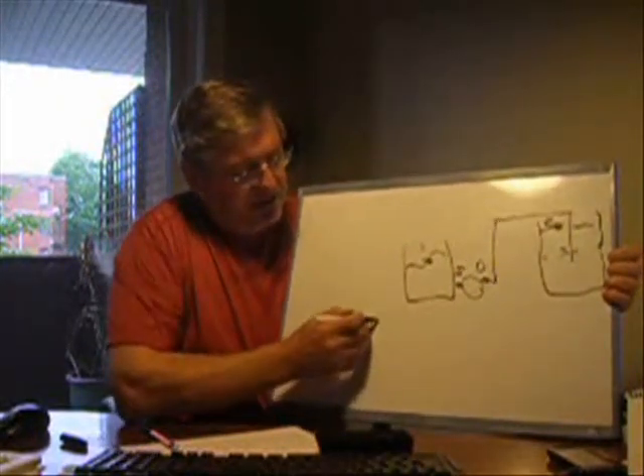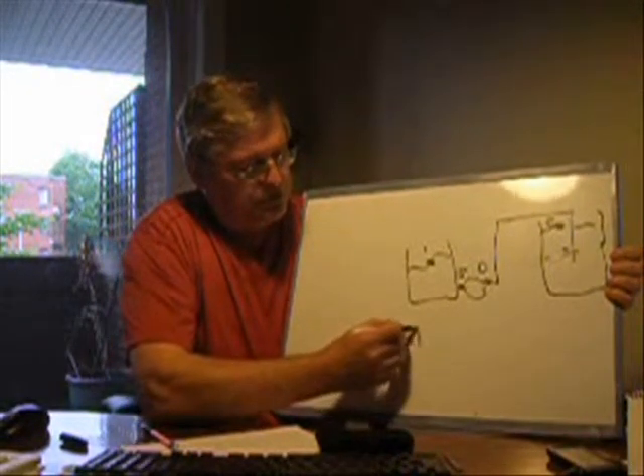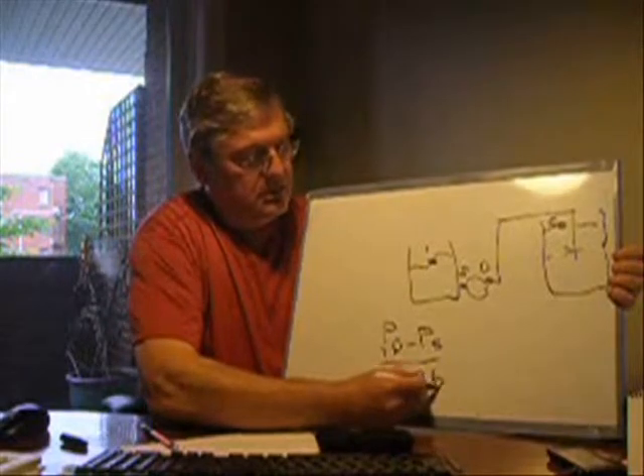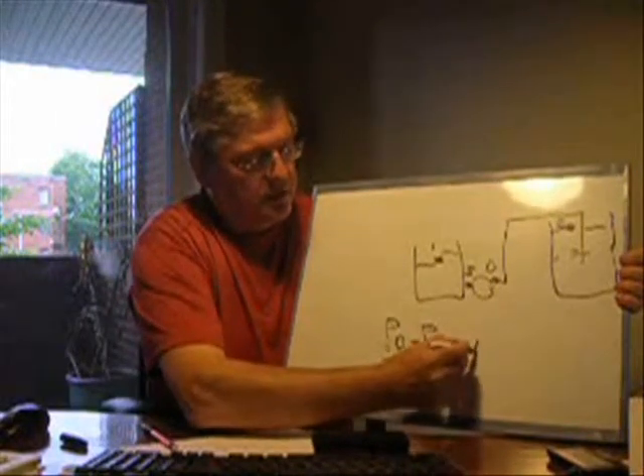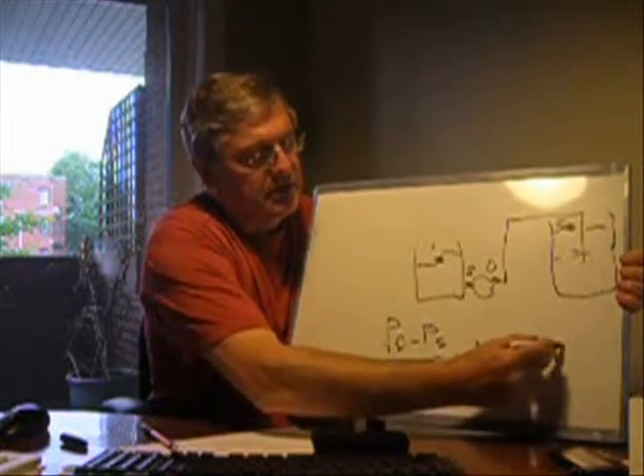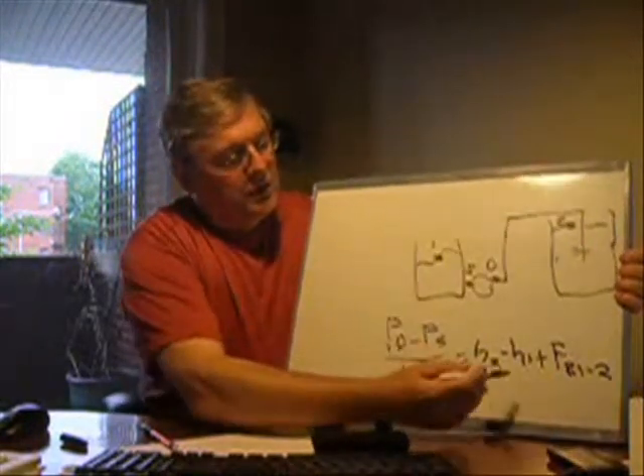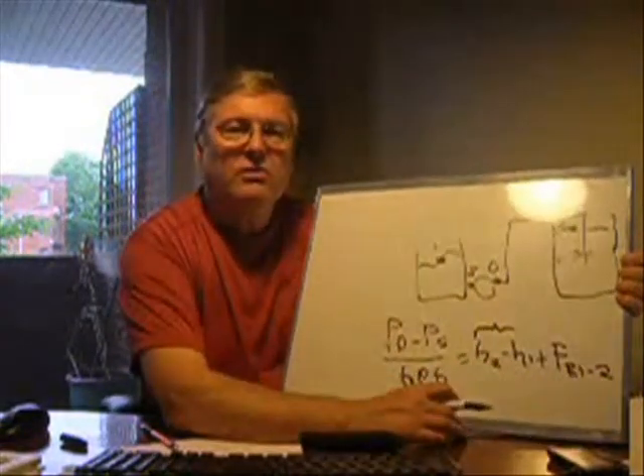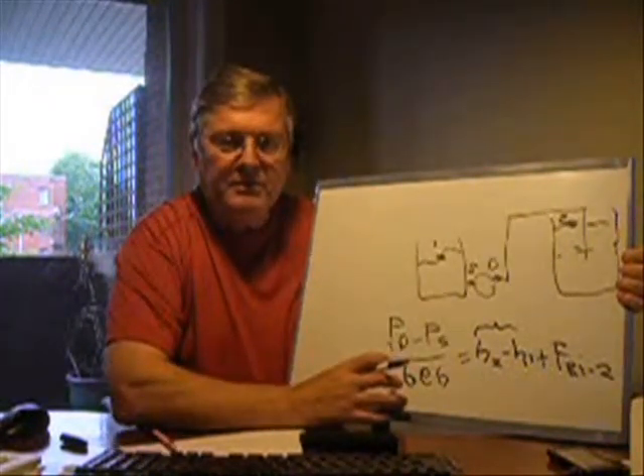The difference in pressure — pressure at D minus pressure at S — divided by density, is going to be equal to the difference in height we need to achieve: getting the water higher up. So that's H2 minus H1 plus the friction head between points 1 and 2. This difference in height is known as static head, and this is called the friction head.